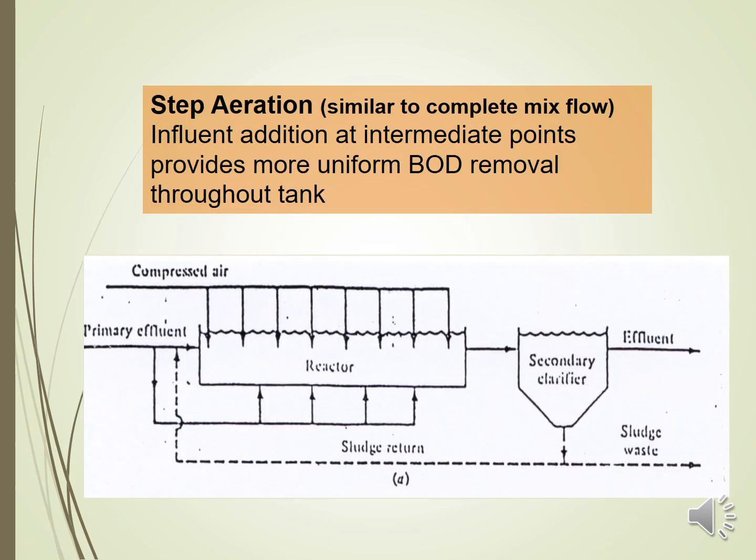Step aeration is similar to a complete mix flow system, where the effluent enters from different sides or points, creating very thorough mixing inside the tank. This makes the F/M ratio uniform throughout the tank and the BOD uniformly distributed. As a result, the air supply throughout the tank is also uniformly distributed, with no difference between inlet and outlet areas.